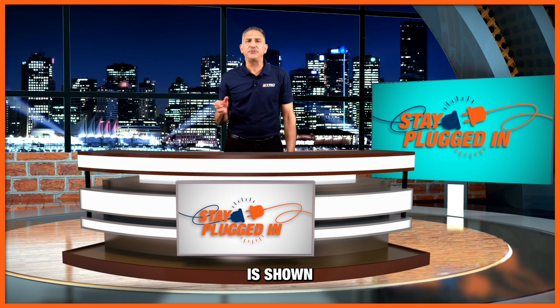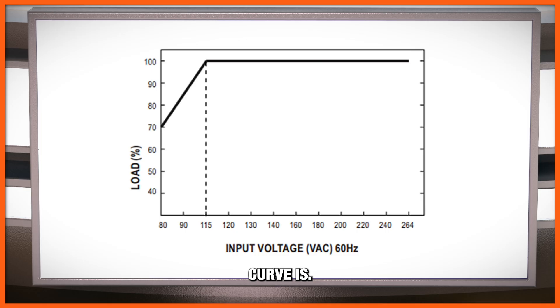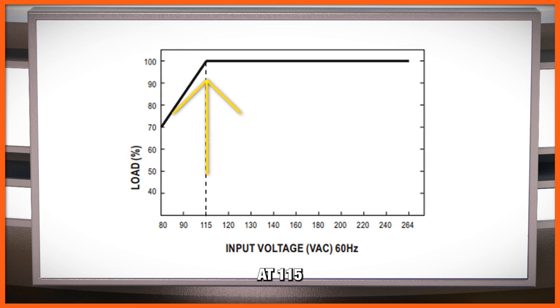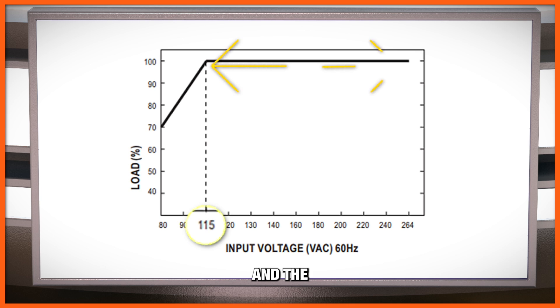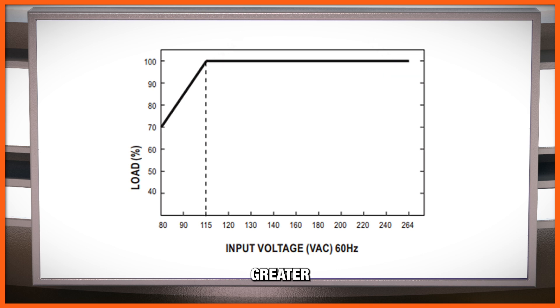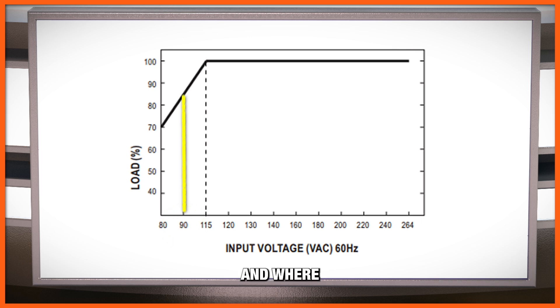The other common shape you'll see in input derating curves has a single flat portion. In this graph, this is a 200-watt power supply, and you can see that you can use 100% of the output power at 115 volts or above, up to the maximum input voltage of 264 volts AC. However, if your input voltage is less than 115 volts but greater than the minimum input of 80 volts, the power supply will function but you will need to derate it. For instance, if your input voltage is at 90 volts AC, draw a line upward from 90 volts AC and where it intersects the curve, that is where your load percentage will be.